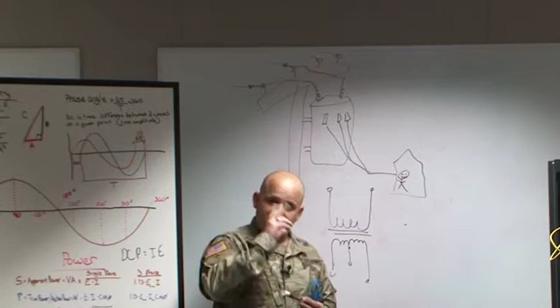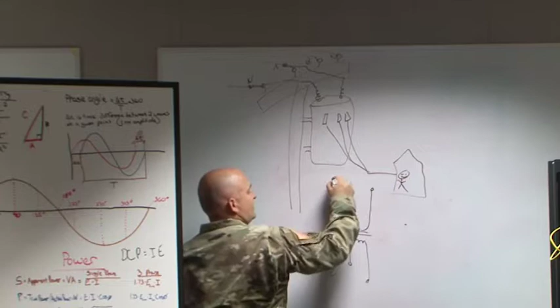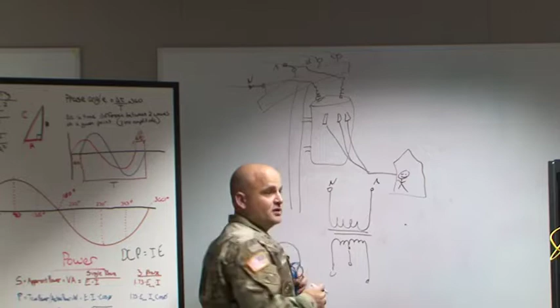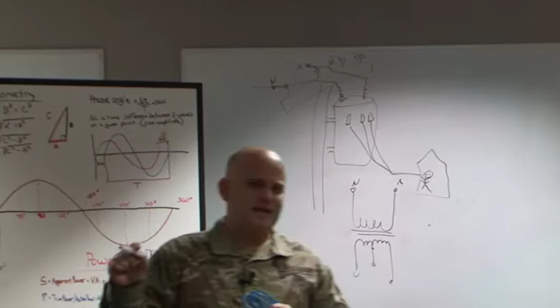If I'm reading a voltage across here, a single phase voltage, and this is my neutral point, which I drew over here as N, A, B, and C, and I'm reading neutral to A here, I'm getting a single phase voltage across here. But just like on that auto transformer, I'm able to tap different voltages off of the same coil. So what does that mean? It means that, say, here to here I'm reading 120 volts, but from here to here I'm reading 240 volts.